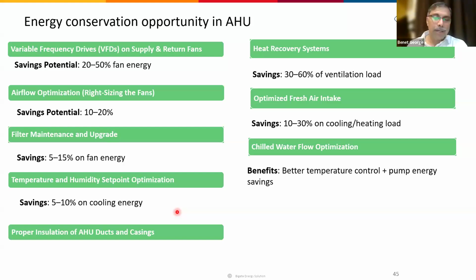Then better ambient conditions. For example, during the cold time, typically like Pune or Bangalore during the winter, we can use fresh air instead of recycling the air in the conditioned space. Fresh air may many times be less than 20 degrees or 15 degrees Celsius also. So you can use those good ambient conditions to reduce the energy consumption.